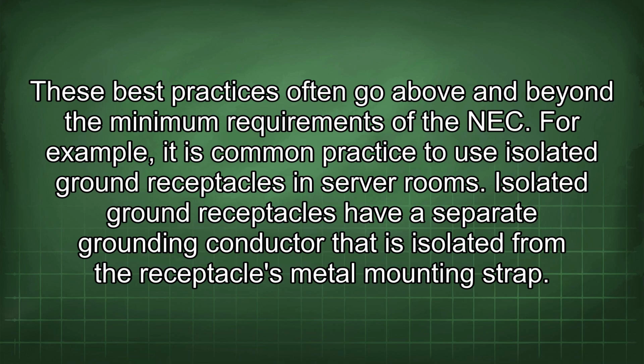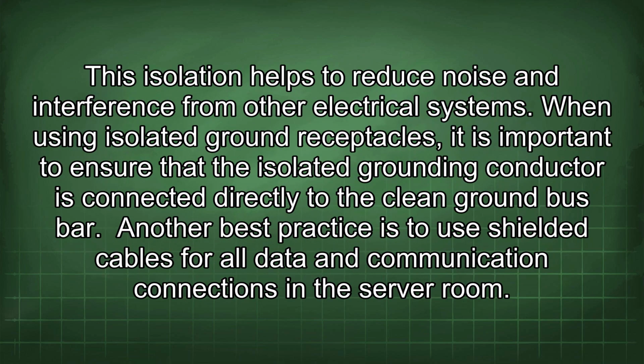Isolated ground receptacles have a separate grounding conductor that is isolated from the receptacle's metal mounting strap. This isolation helps to reduce noise and interference from other electrical systems. When using isolated ground receptacles, it is important to ensure that the isolated grounding conductor is connected directly to the clean ground bus bar.